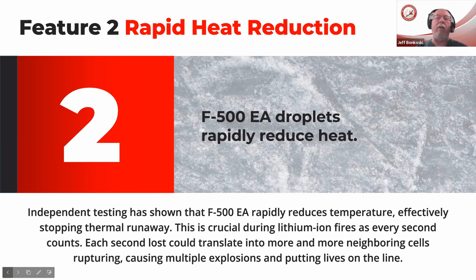That's one of the main things we keep hearing about, thermal propagation, that goes from battery to battery to battery. If we can cool down and stop the thermal runaway within a battery and stop the thermal propagation within a module or cell, that's being able to stop that fire from continuing to burn on. So now we look at the toxins being released.